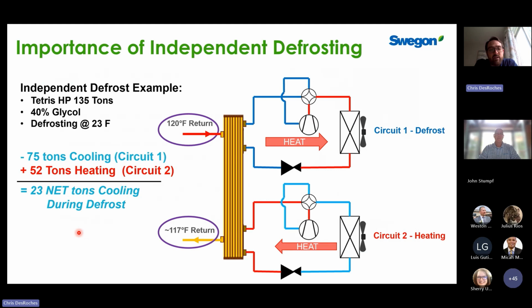And to explain this and put some numbers to it, I got a chart on the next slide to show this, and this is really the reason why independent defrosting is very important. By having two refrigerant circuits and being able to defrost them one at a time, we can mitigate the effects of defrost that we're going to see.